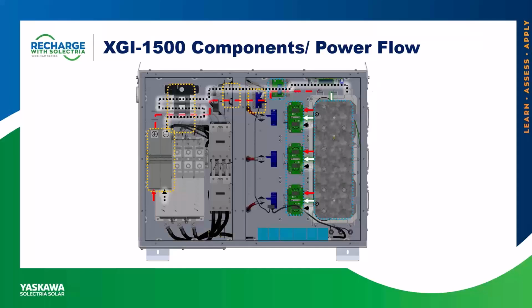So basically, first it all starts with your DC terminal block. The customer lands the positive and negative feeders coming from their combiner box on the array side on that terminal block. And basically, this is a DC powered inverter. What that means is if we don't have any DC voltage present, the unit is going to automatically shut down. You're not going to have any lights, LEDs on the inverter or anything like that. It's not powered off AC, but DC.